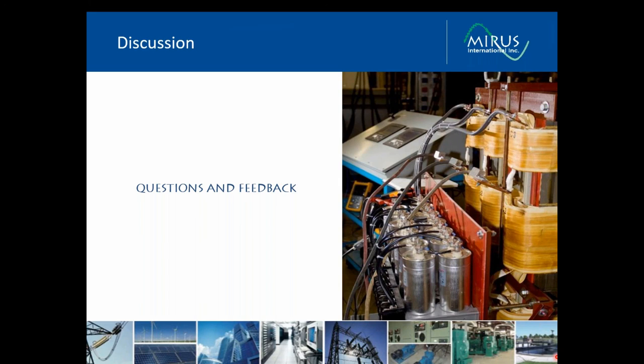And we need to understand that high-frequency harmonics are much more of a problem on our power system than the lower frequency harmonics. Voltage distortion, it's a lot easier to get voltage distortion when you're dealing with the higher frequencies on the power systems because the impedance of the power system is higher due to the frequency. And when you have these higher frequency distortion levels, the connected equipment is much more sensitive to the high frequency levels as well. So it's a real problem, often ignored, one that we all need to be aware of.